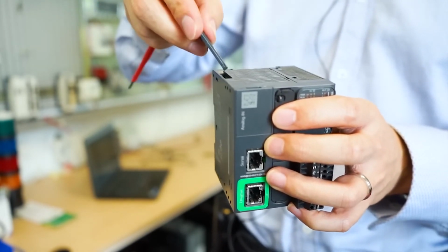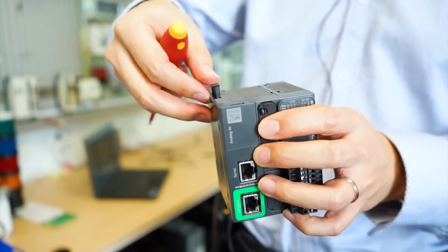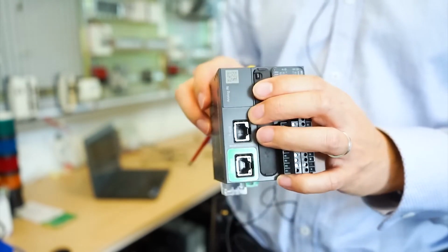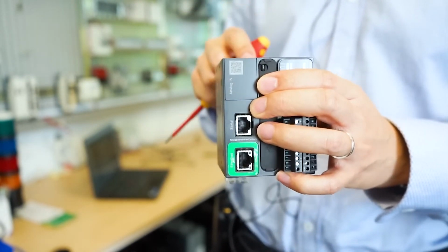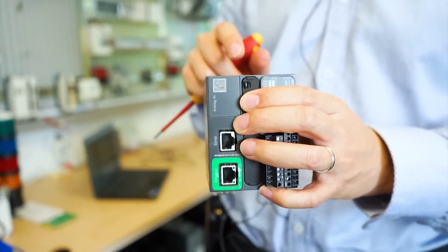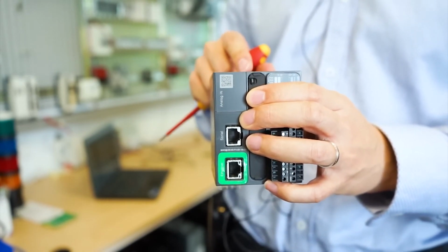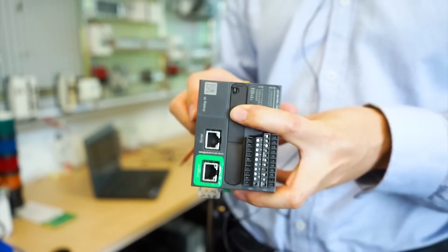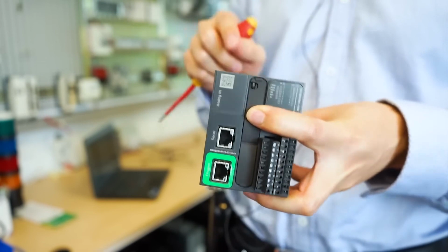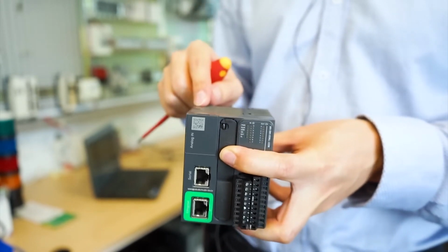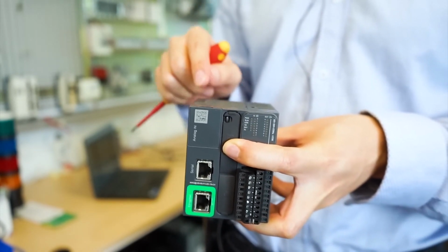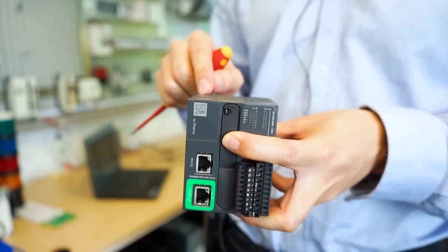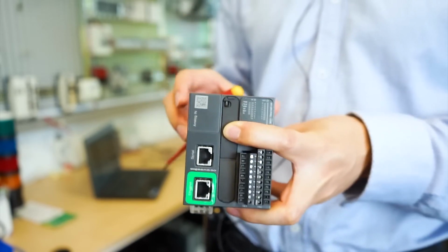The reason we have this battery here is because we have a real-time clock built into this controller, so we can use the battery to maintain the RTC and also to save all the data if a power interruption happens. The backup life for this battery is at least 1 year at 25° maximum.